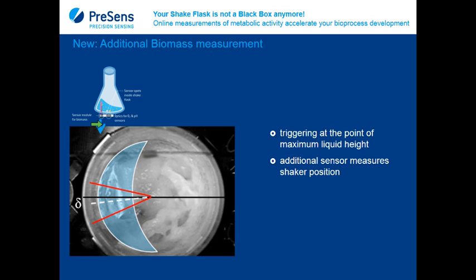And is it possible to use colored glass? Good question. I think this really depends on the color. If we are talking about a brownish color like maybe a typical beer bottle, it will be difficult because then we are losing too much light. If we are talking about maybe a more yellowish flask, then it's possible, it just needs adjustment of the calibration settings. Okay, and one more question about the calibration. Are these sensors single-use or multi-use? And if they're multi-use, do the sensors need calibration?